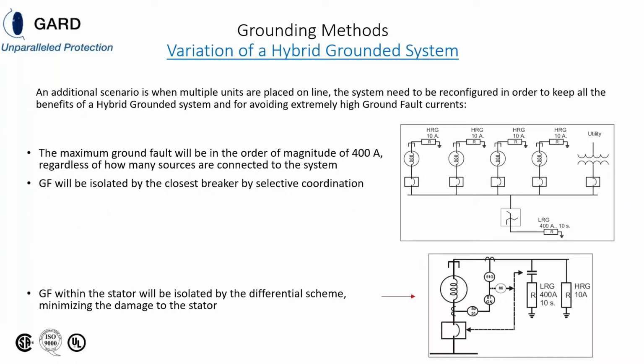A variation of this is to use a zigzag on the bus. And I said to use a zigzag on the bus because it minimizes the fault current and is less complexity in the design. In this setup, you can add more generators and just put a 10 amp resistor on each generator. But in this design, there's more complexity in the contactor and differential protection. Well, mind you, you're going to have differential protection up there as well.